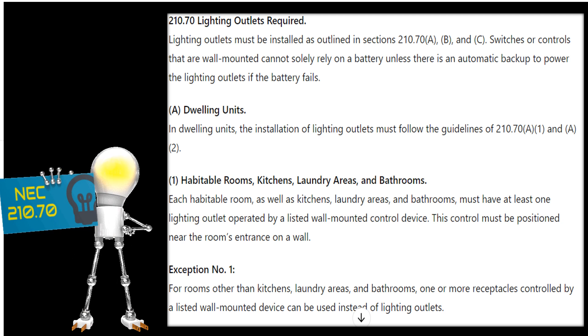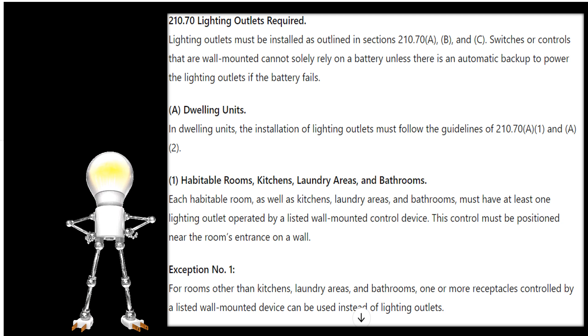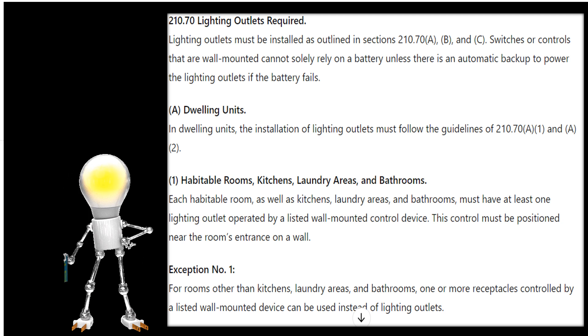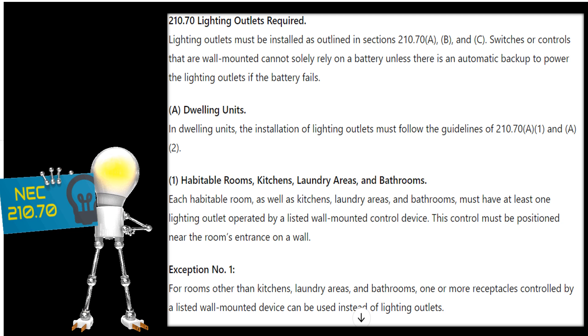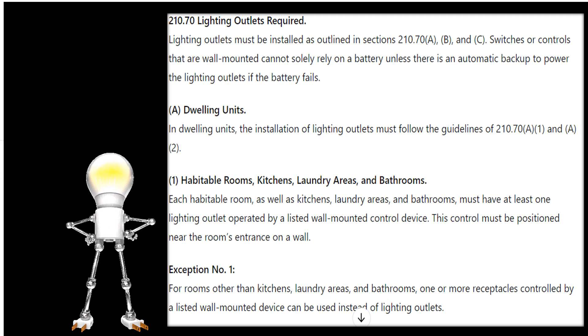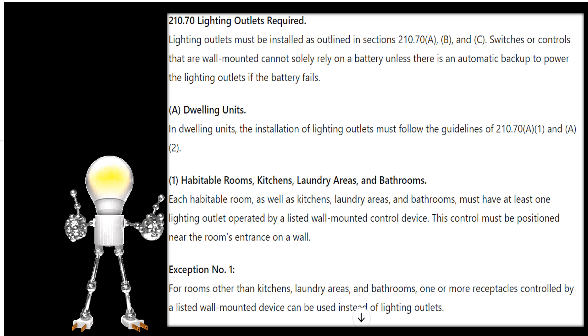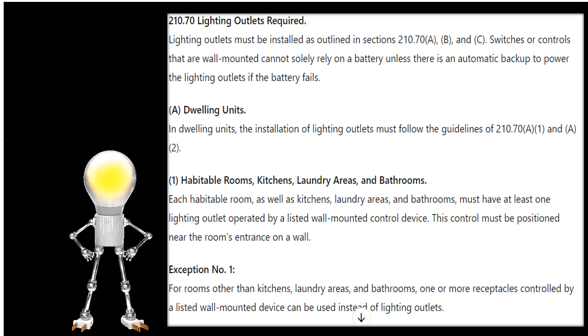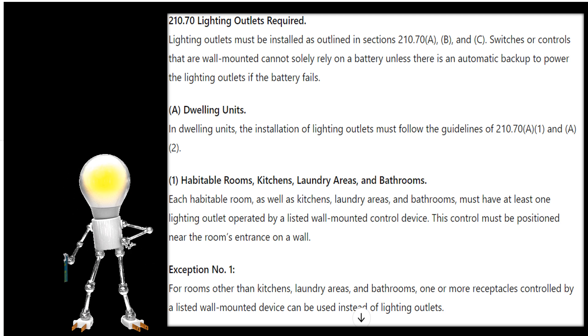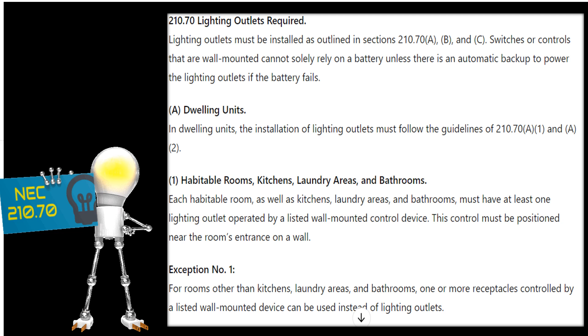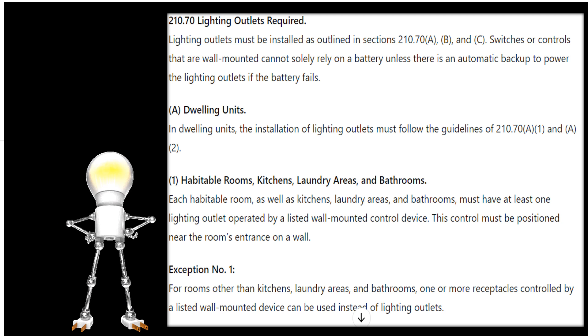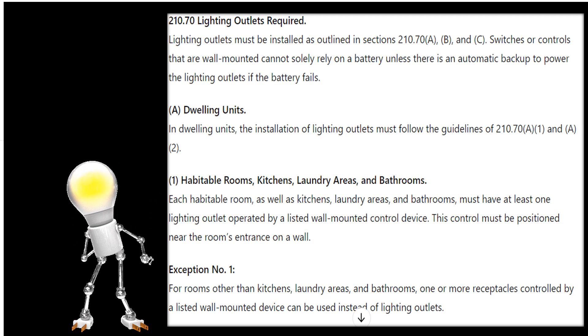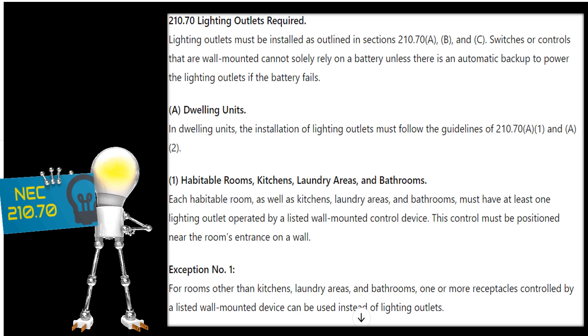In Section A1, it says: in dwelling units, the installation of lighting outlets must follow the guidelines of parts A1 and A2. Looking at A1 — habitable rooms, which is a defined term, kitchens, laundry areas, and bathrooms — each must have at least one lighting outlet operated by a listed wall-mounted control device, positioned near the room's entrance on the wall.